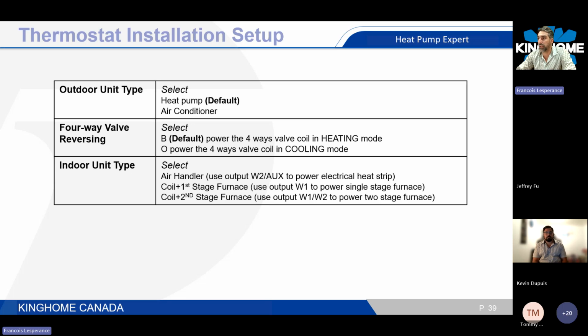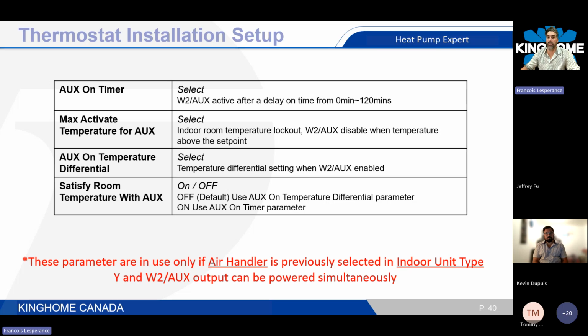Indoor unit type, there's 3 indoor unit types. By default, we're going to use an air handler, so you have to make that change to put it on a single stage furnace or a 2-stage furnace. Inside the installation setup, there's some adjustment dedicated only for air handler. And there's another slide, which we're going to see right after, that is only dedicated to furnace. So you have to be aware of it. You have to make sure you understand it properly. When you see aux, this is dedicated for air handler indoor unit. So if you have selected a gas furnace, for example, then those setups won't work, typically.